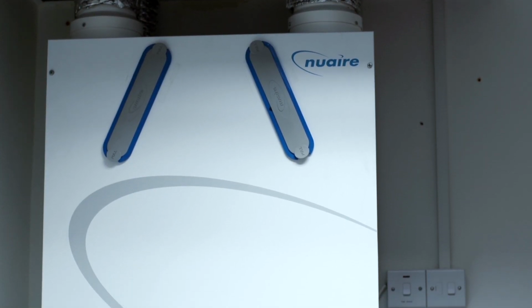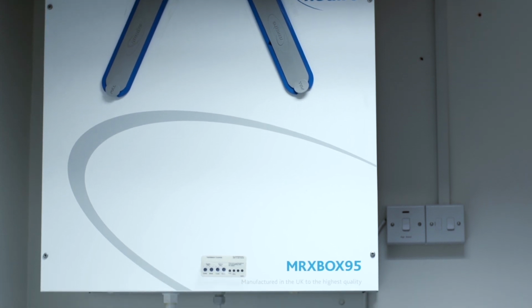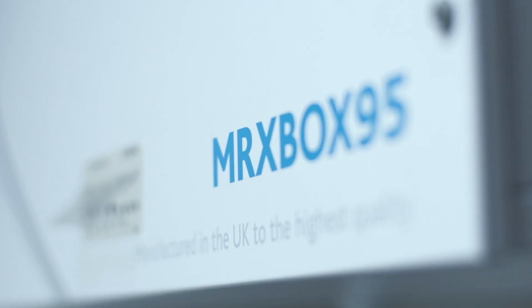When it comes to actually installing a heat recovery system, ensure that the wall it's going to be installed onto can support its weight. If the system is going to be installed on plasterboard, make sure that you use a pattress at the back just to give that added strength. Manual boost switches are required in all the wet areas such as the kitchen, bathroom, ensuite and utilities.